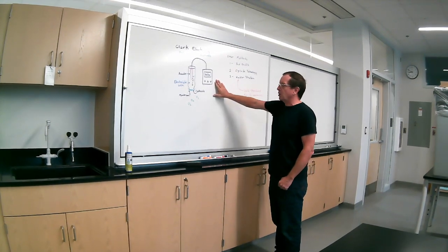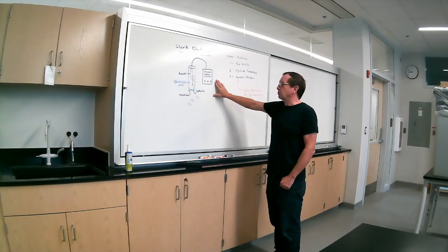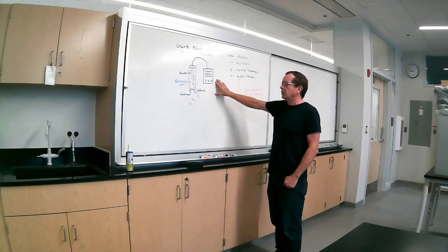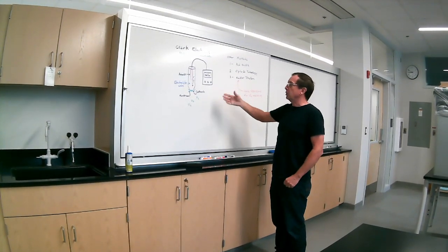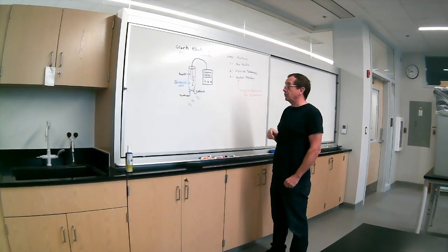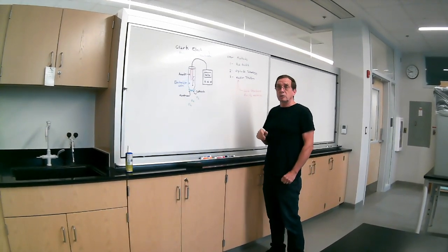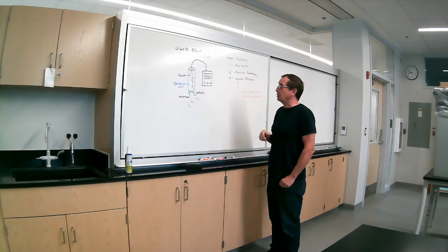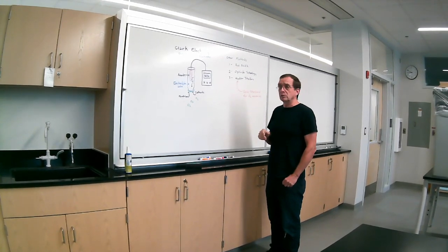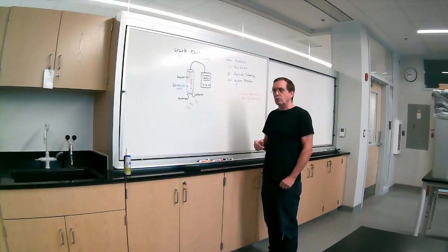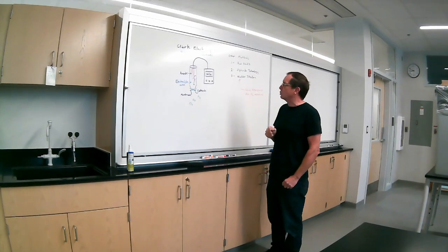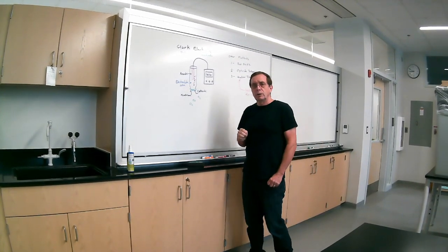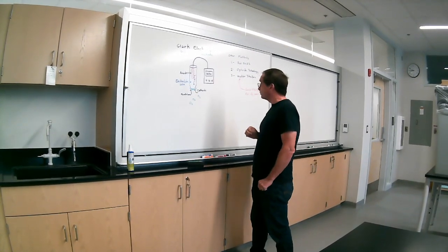So this has been the standard for a long, long time. Again, we used to make our own way back, 60 years ago or so. And then companies started to produce them. The Yellow Springs Instrument Company is probably the most famous, and they have made all sorts of field units where you can take them out. They're really rugged, they're really dependable. As long as you take care of the electrodes and re-membrane it occasionally, and calibrate them carefully, then you get some pretty good numbers from it.